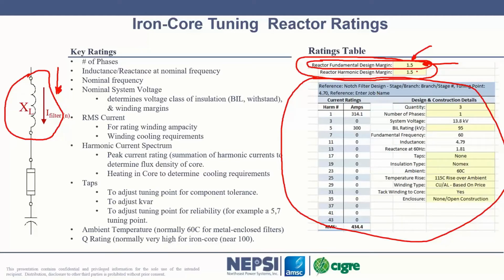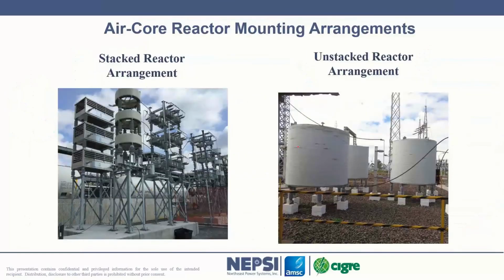So we go with a 1.5 multiplier on the current, and then we decide from there how to rate the protective devices. So if we take our harmonic currents and multiply by 1.5, it means we can set our protection devices at 1.0 per unit current. So that is kind of our philosophy.